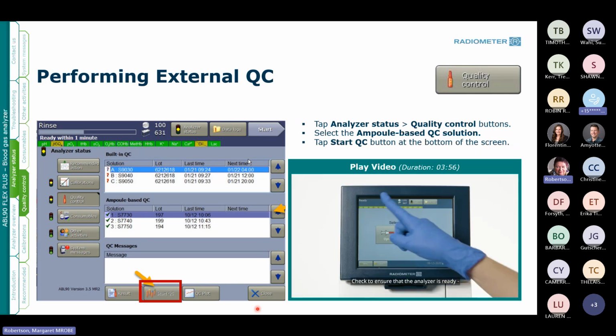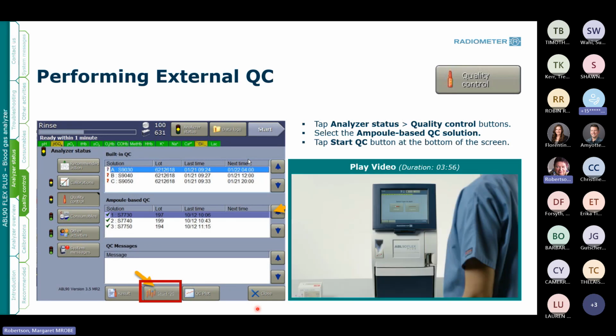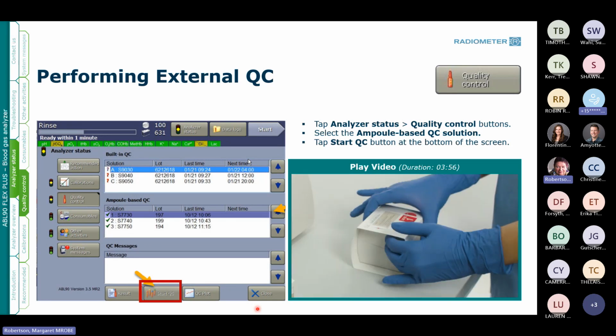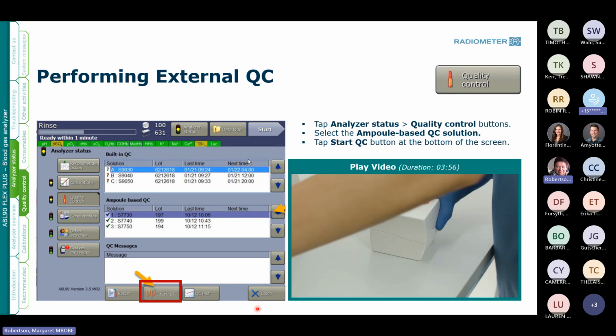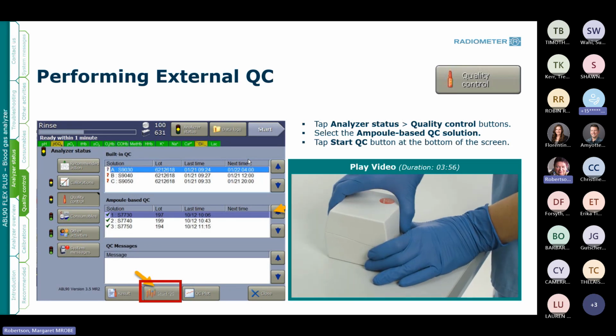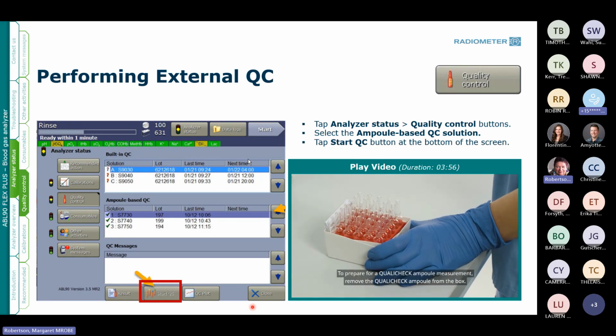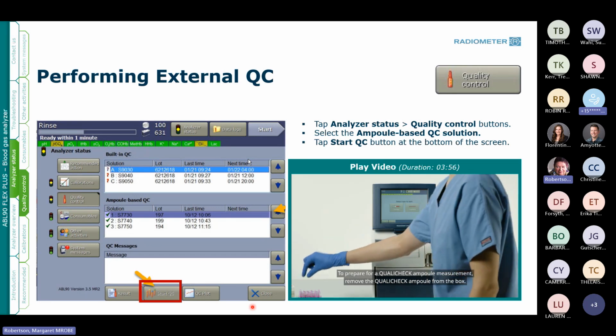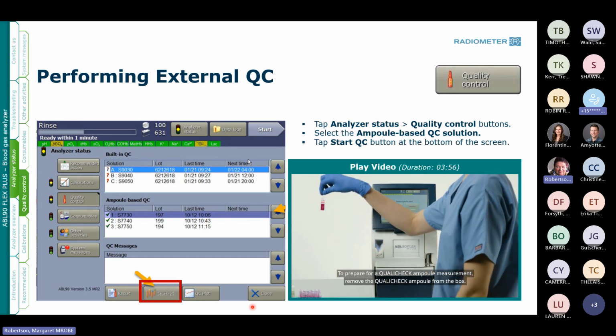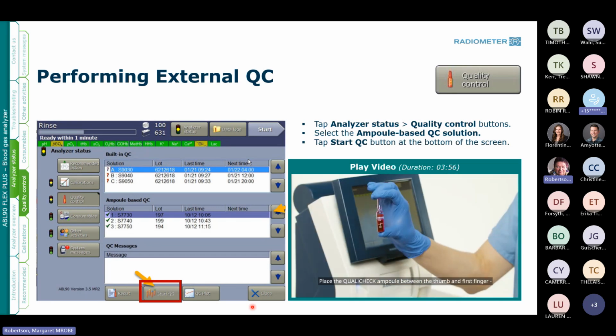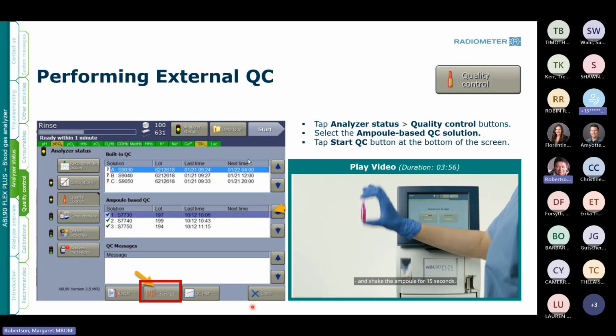Check to ensure that the analyzer is ready and that all parameters are green. This means that internal calibrations and quality controls have passed. To prepare for a QualiCheck ampoule measurement, remove the QualiCheck ampoule from the box. Place the QualiCheck ampoule between the thumb and first finger to avoid changing the ampoule's internal temperature, and shake the ampoule for 15 seconds.